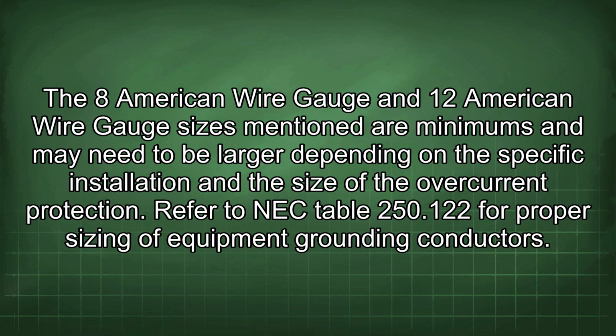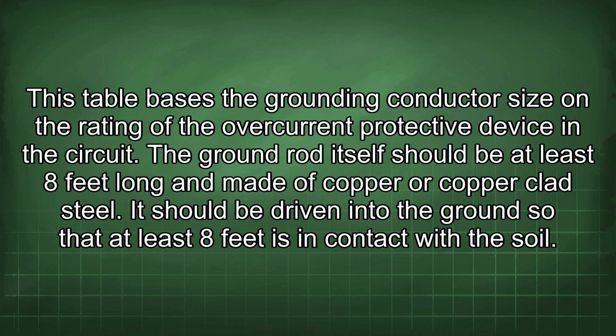Refer to NEC Table 250.122 for proper sizing of equipment grounding conductors. This table bases the grounding conductor size on the rating of the overcurrent protective device in the circuit. The ground rod itself should be at least 8 feet long and made of copper or copper-clad steel. It should be driven into the ground so that at least 8 feet is in contact with the soil.